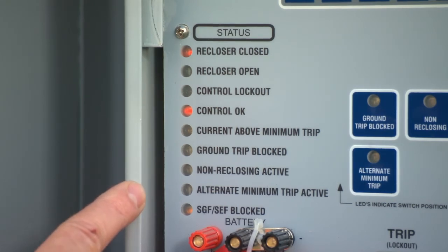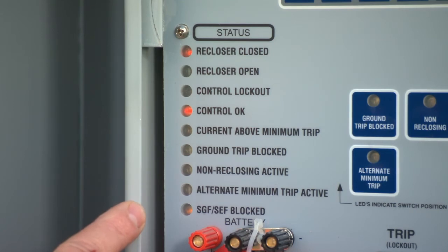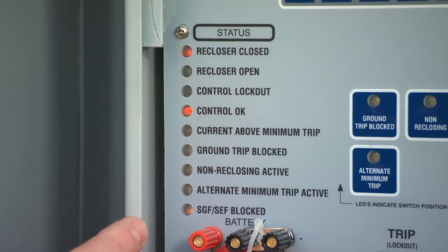Alternate minimum settings is a second settings group in the control that can be activated by pushing the alternate minimum trip button. The light will turn amber. On the bottom is an SGF-SEF sensitive earth fault. This is currently blocked or turned off within the control, and so it illuminates amber.